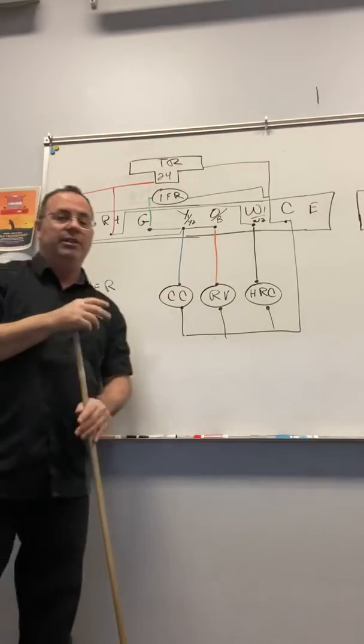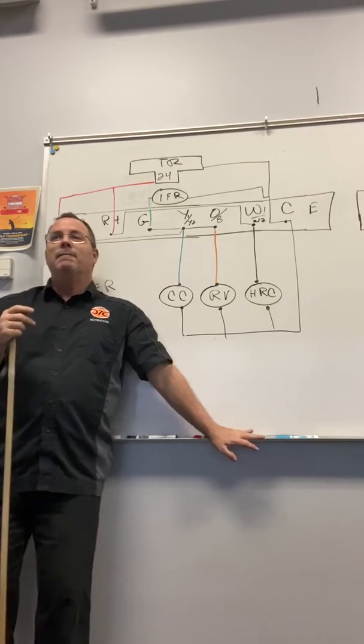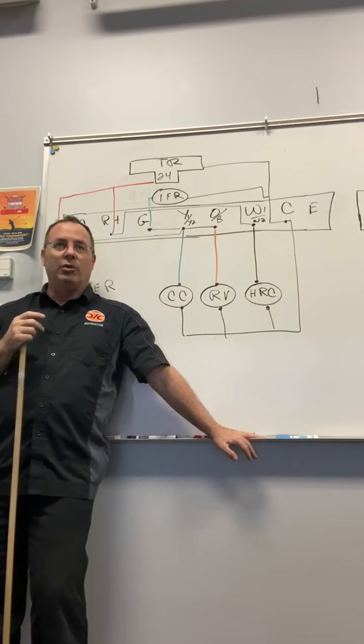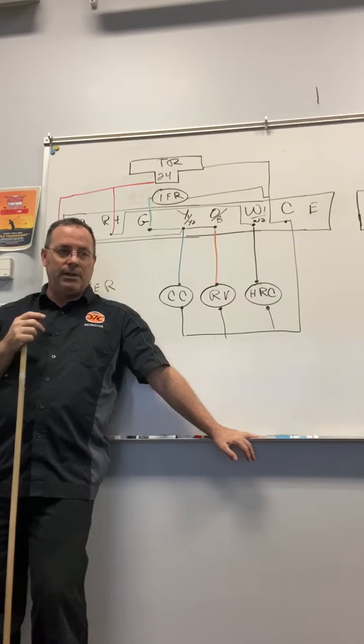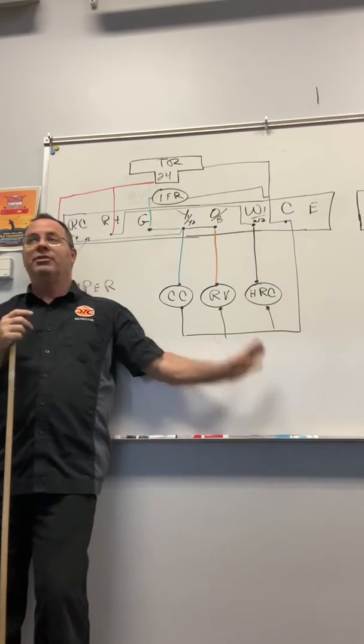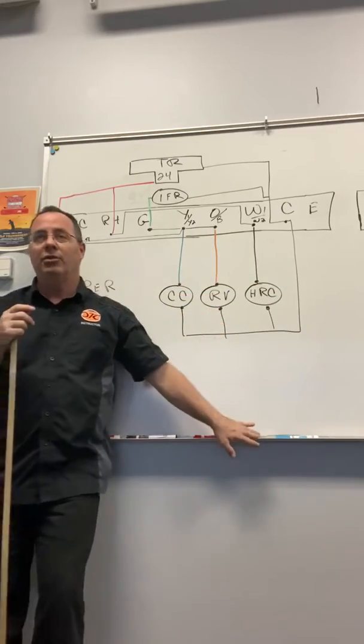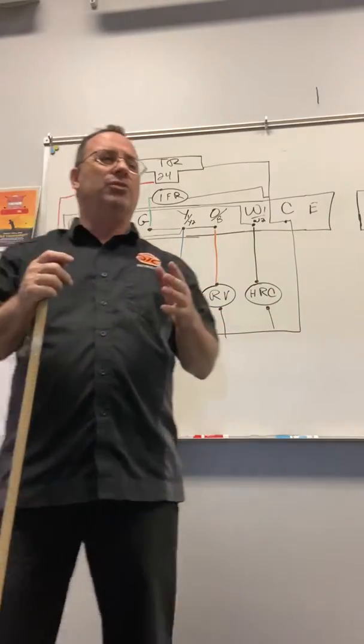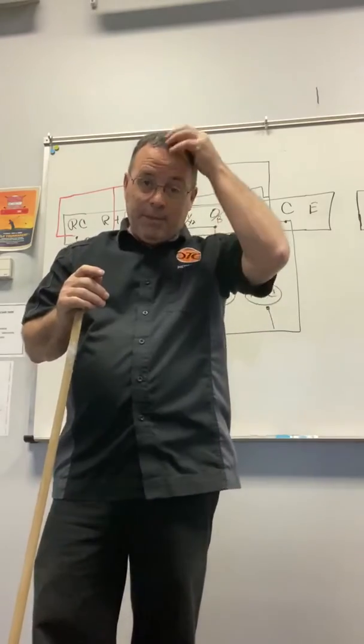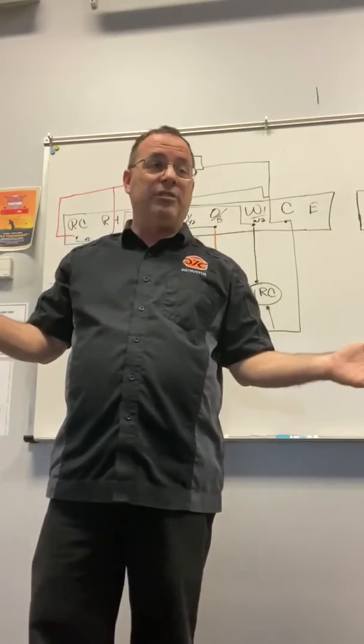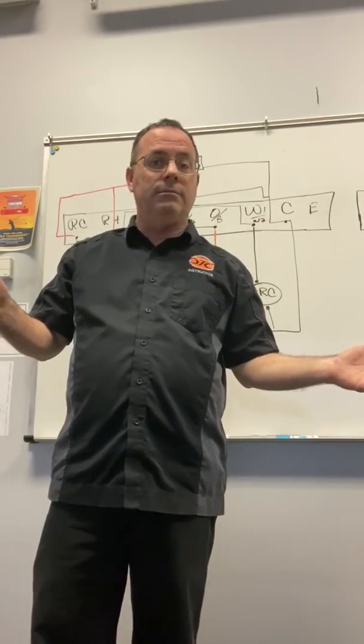But some units, because they're really big or they have a long run, will have an outdoor transformer too. And that can get really confusing for guys out in the field. You have one transformer indoors and you have an outdoor transformer. Well, the outdoor transformer, look at it like this. If it's in the condensing unit, it must have something to do with the condensing unit. So let's go ahead and look at that now.